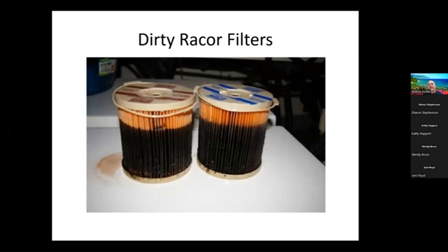All right. Now, again, we're back to the Racor filters. If the filters look like this, you need to change them a little more often. But this also tells you that you have a lot of sediment and growth in your fuel tanks. A lot of this here is just algae. Now, the misconception is that you can put Algae-X or Biobor in a fuel tank and it'll kill the algae, but it won't get rid of it. Algae-X is a good preventative, but if you're getting filters that look like this, you're probably going to need to have your fuel tank pumped out, cleaned, and start over, and then start adding your Biobor or your additives.